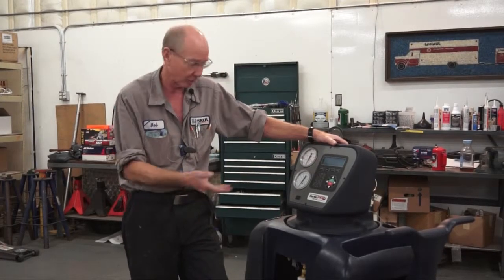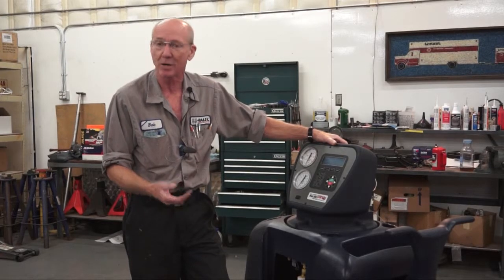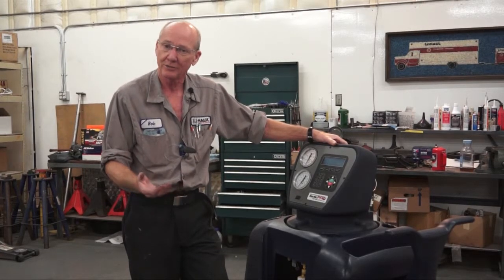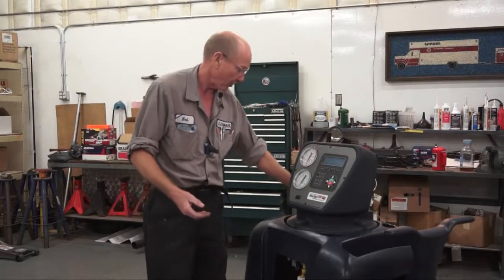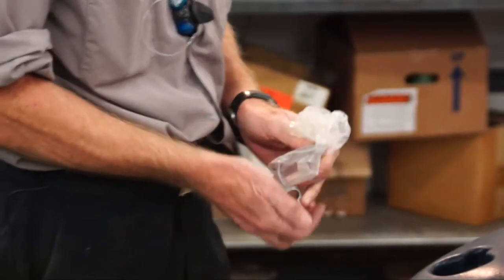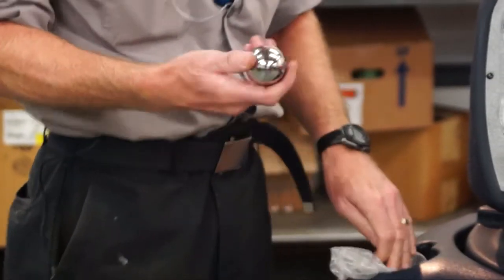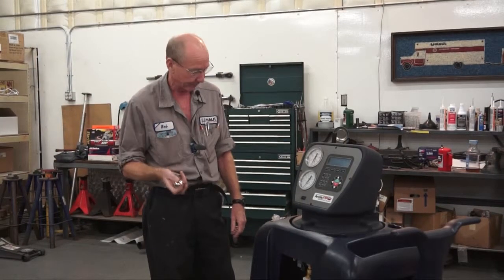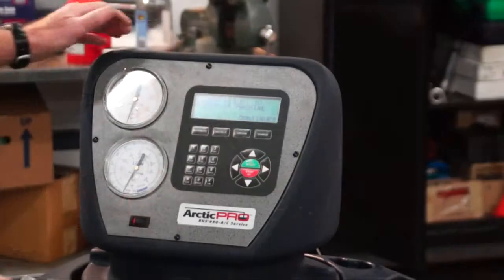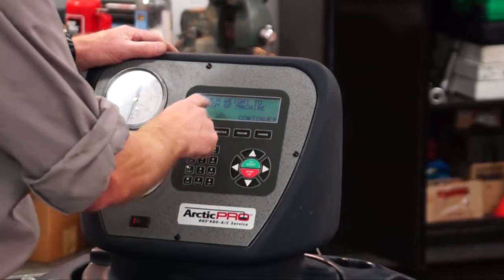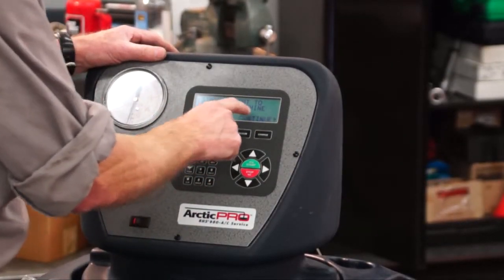You can do that because that's going to be the first prompt that comes up prior to getting to the vacuum pump oil. It's very easy to do. Your machine comes with a steel ball. I keep it in a plastic bag because it keeps the corrosion off the ball. You want to keep it clean, nick-free. So I'm going to select yes. Then it's going to prompt me here. It says attach weight to bottom of the machine.